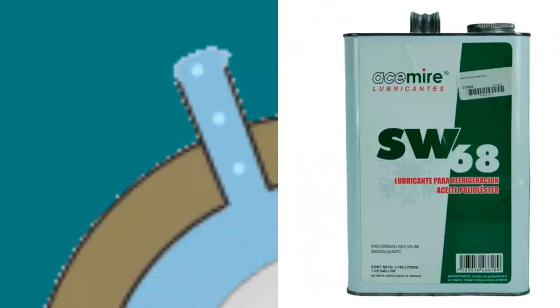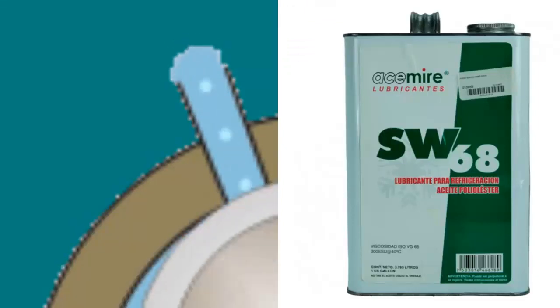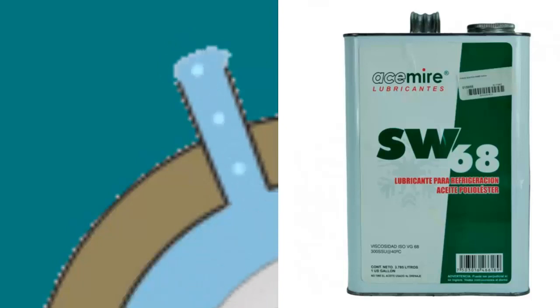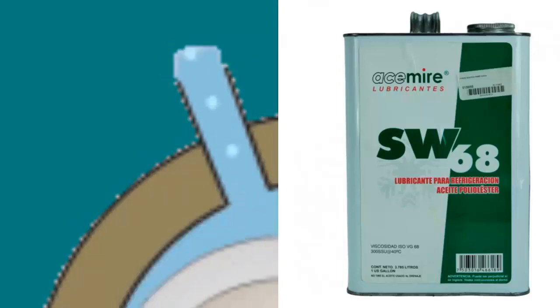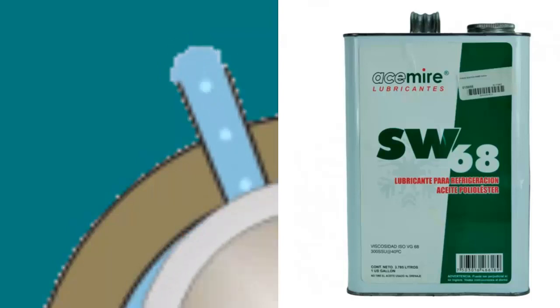The POE-68 oil has a viscosity close to 68 centistokes at 40 degrees Celsius, which ensures optimal performance at the working temperatures of the refrigerant and the equipment.